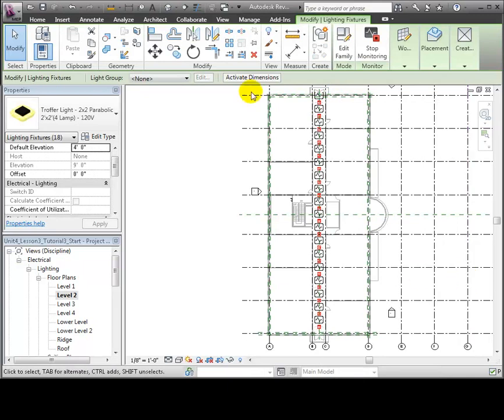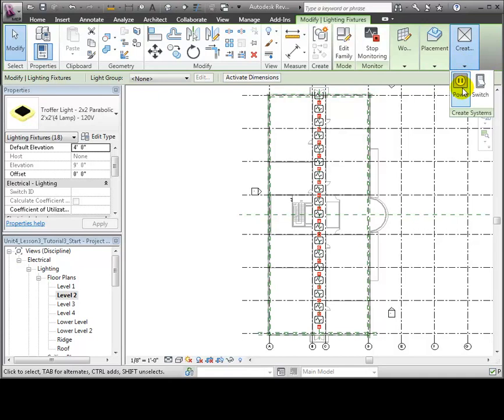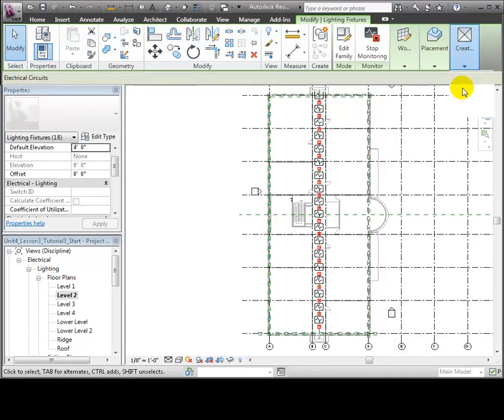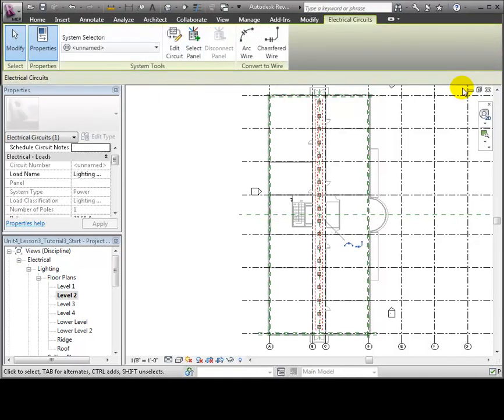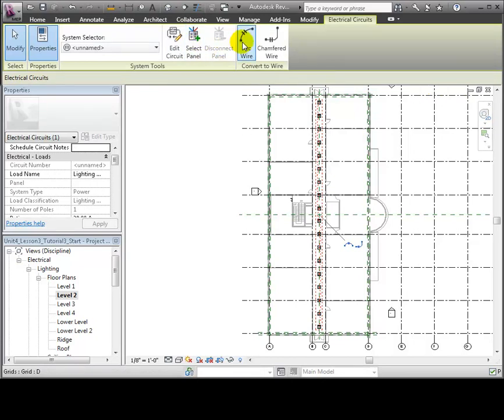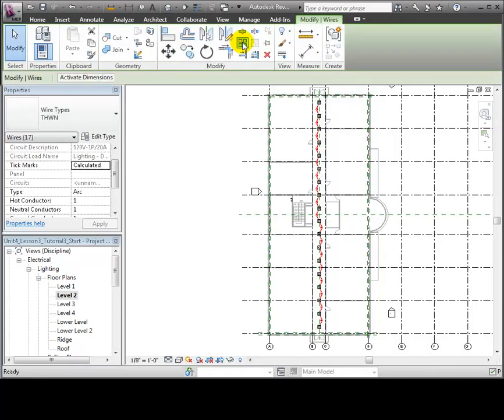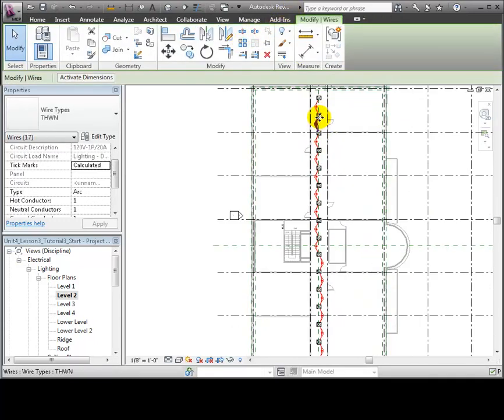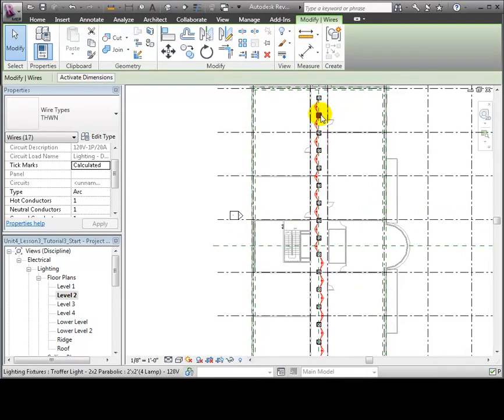The Modify Lighting Fixtures tab appears and we can choose to create a new power or switch system for these lights. Let's use the Create Power System tool and the Electrical Circuits tab appears with options for creating the circuit. We'll start by showing the wire connections between the fixtures using the arc wire convention to specify that these wires will be concealed. Arc wire segments appear between all of the selected light fixtures showing that they are connected into a circuit.